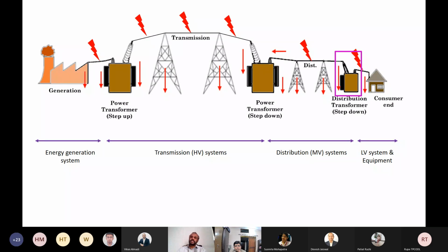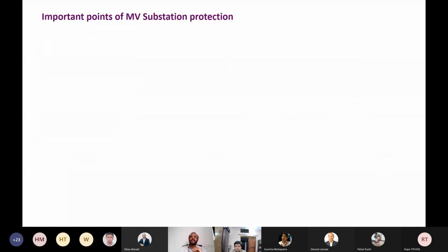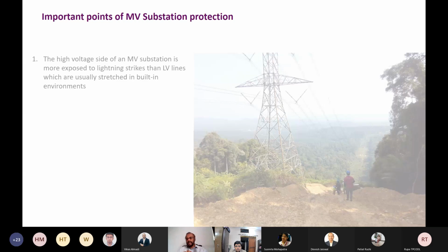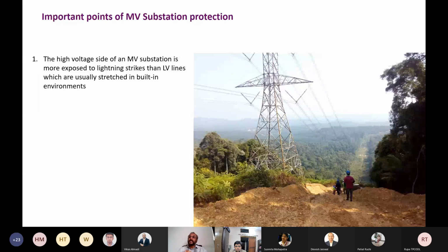And I'm not touching the HV side as well as the consumer side or the LV side, which we can cover on another occasion. Now, what are the important points of MV substation protection? When it comes to the lightning protection of MV systems compared to LV systems, we have a few differences. One is the high voltage side of an MV substation is more exposed to lightning strikes than LV lines, because the lines are stretched over a very large area, so the chances of lightning transients coming from the HV side of the substation are much higher than from the LV side.